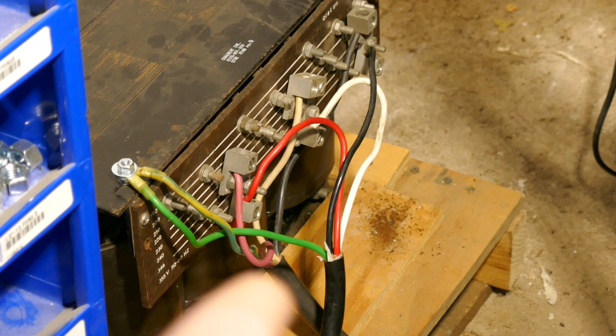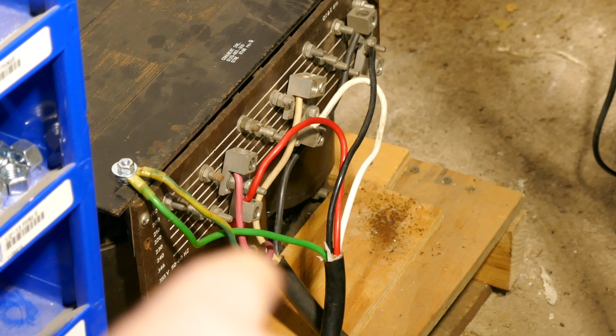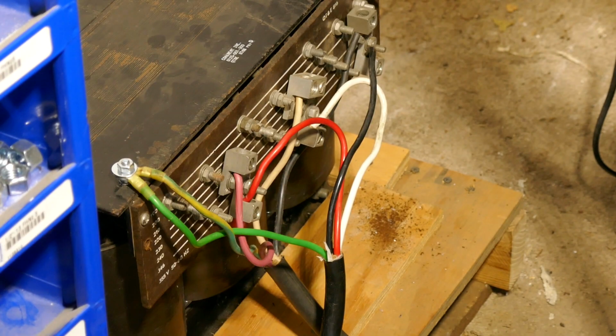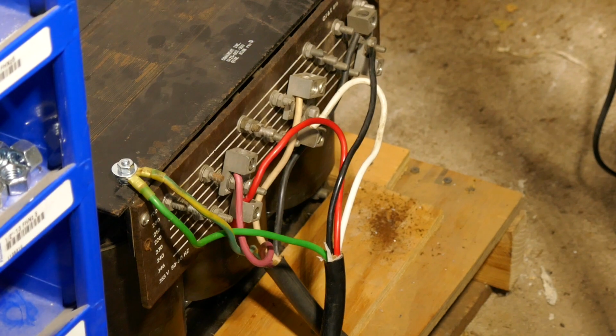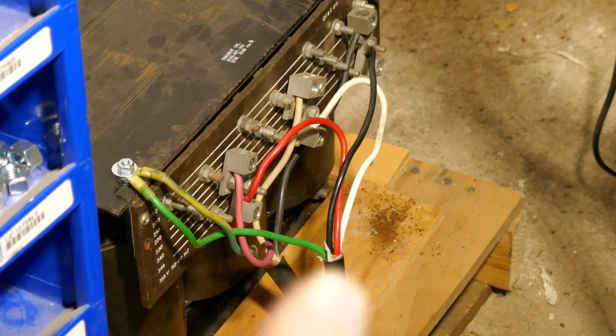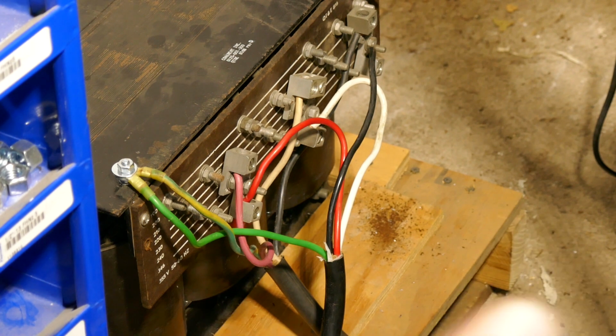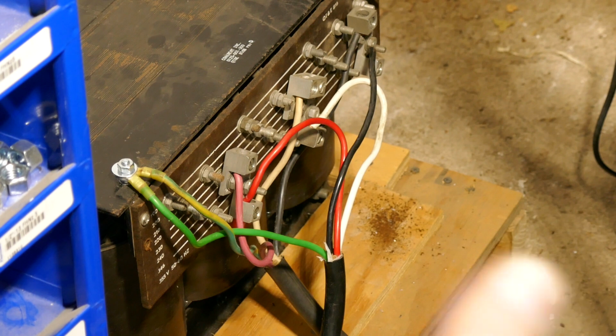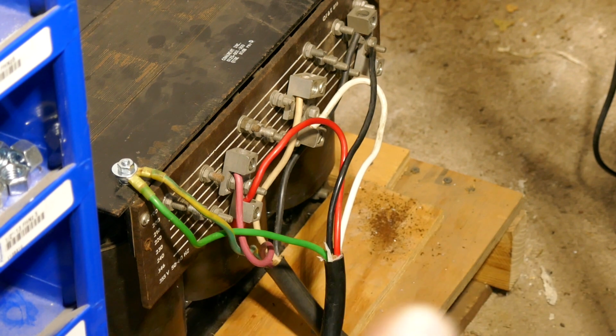That cable right there, going out of frame, then goes to the machine, and this goes in place. What I've done is added a grounding lug to the frame of the transformer so I can bring ground in and send ground out. This transformer was most likely grounded on the frame because it was mounted to a chassis, and I'm sure the chassis was grounded. So this was inside a big metal cabinet at one time.